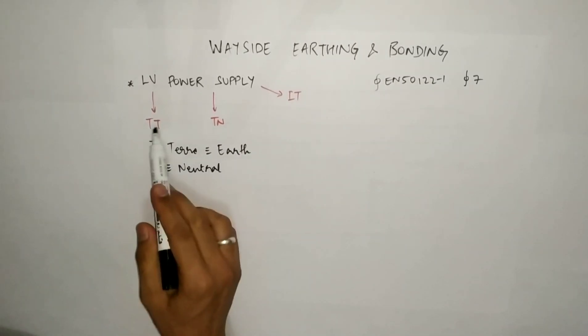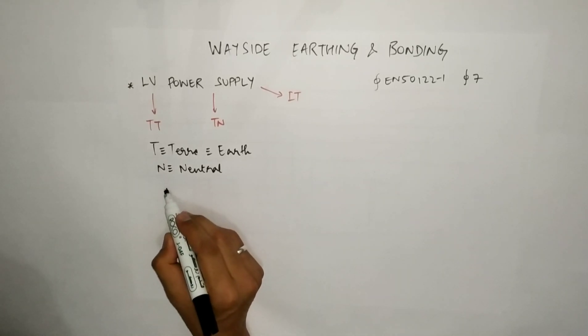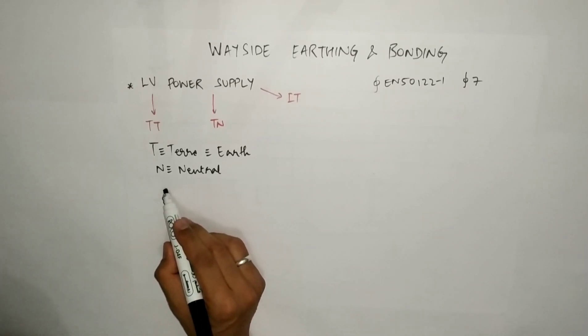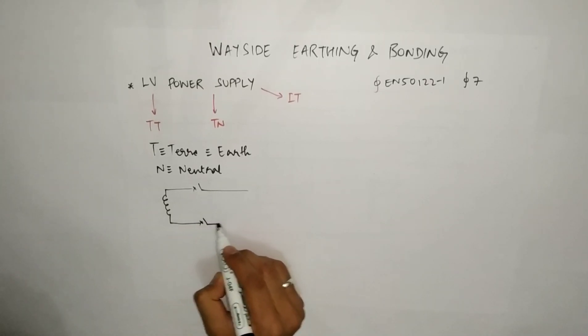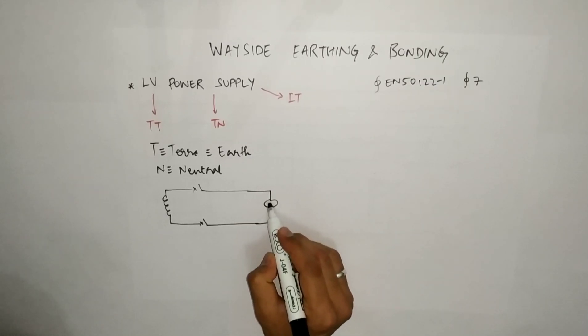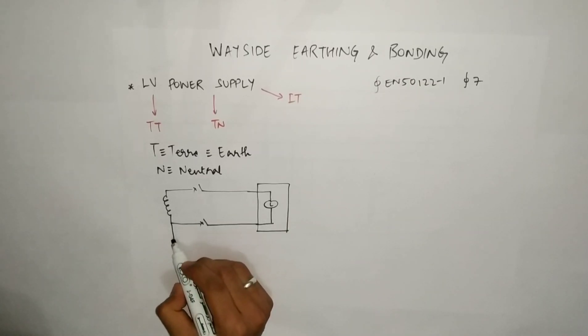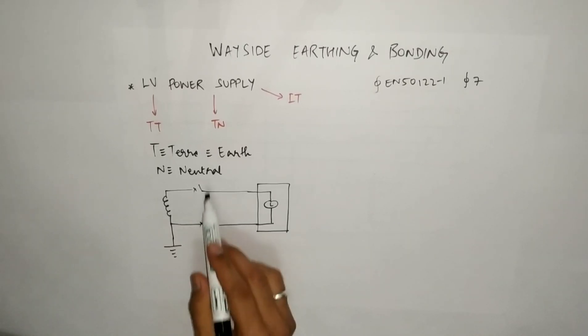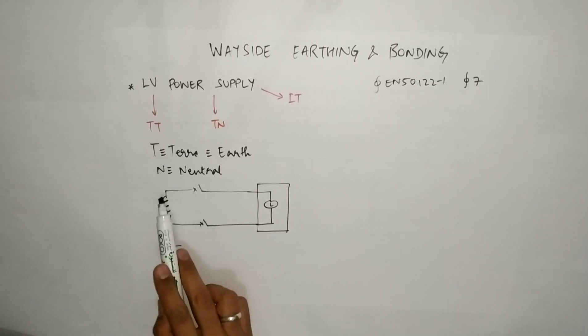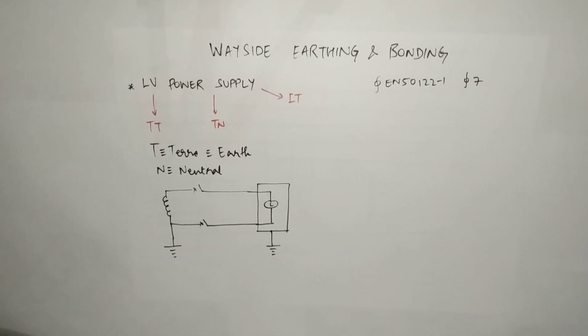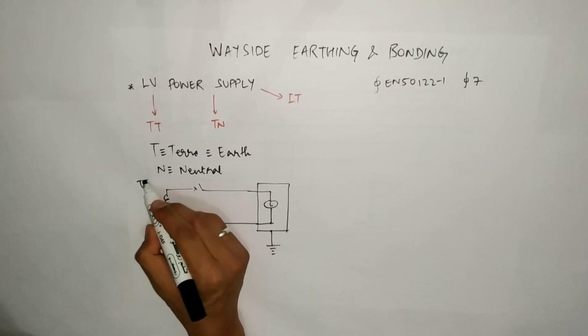Let us first go for TT. In this case, this is the secondary of the transformer — this is your source from where the LV power supply is coming. Then you have a breaker and it is directly fed to the load. This is the enclosure of your load or equipment, and it is connected to the earth at the source end. There is no separate transformer in between. The LV power comes directly to the equipment, and this equipment is also connected to earth, but completely separate from the source earth. This connection is the TT connection.